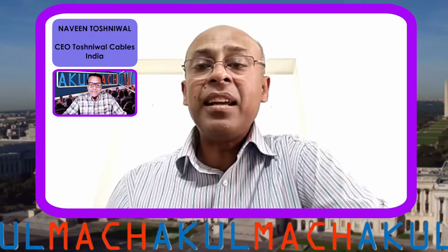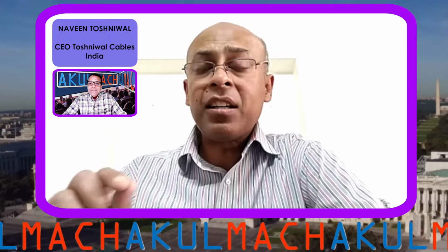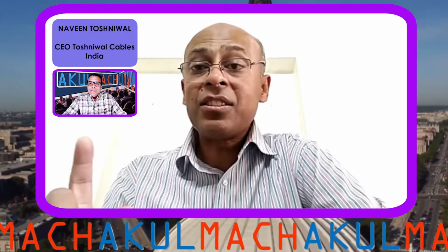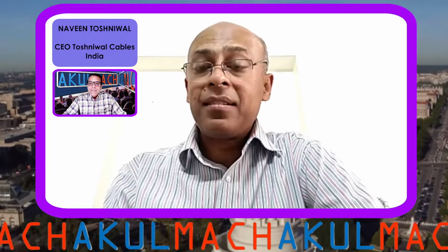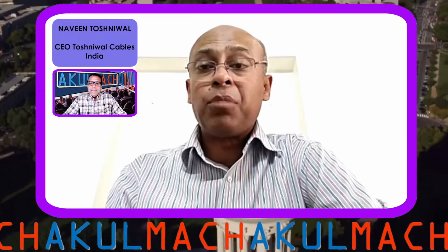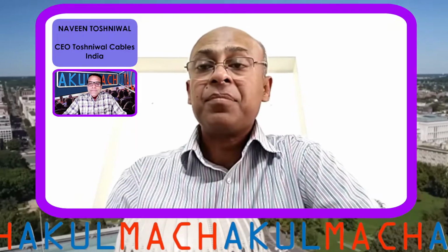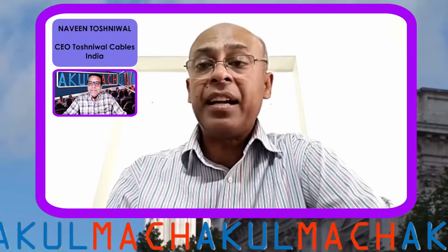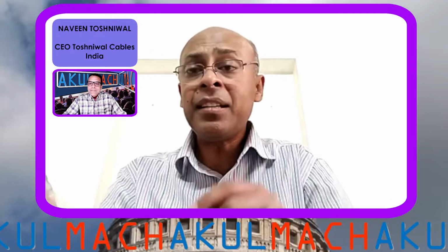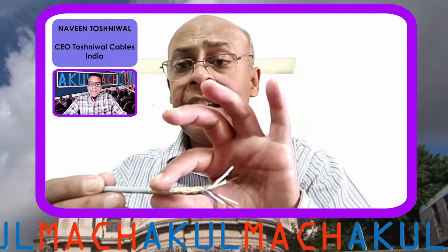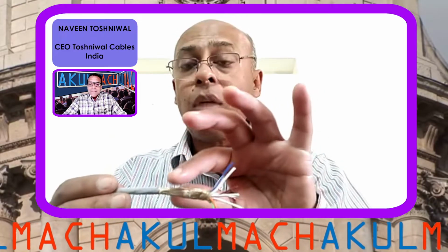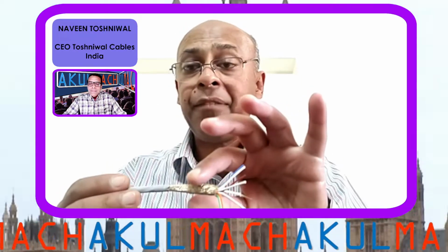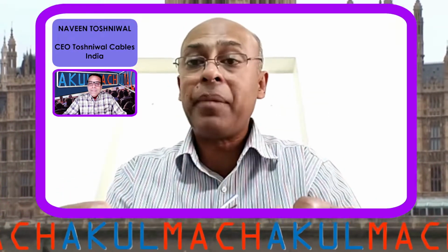No, actually, silver is basically meant to cover the copper so that it does not burn or melt during the sintering process of the outer sheath. It has nothing to do with the electrostatic shielding. Shielding is done by the copper itself. The coating is just to give it a protection so that the copper is not oxidized, and if it is of tin, the tinning should not melt.